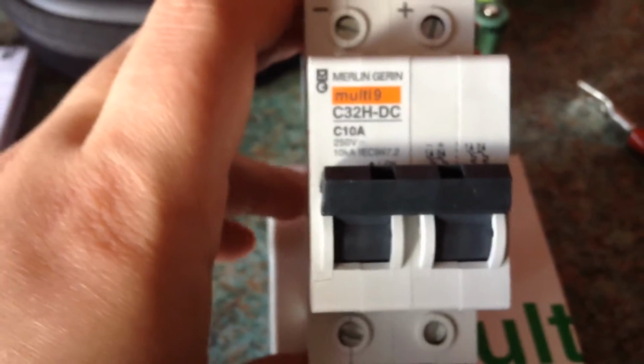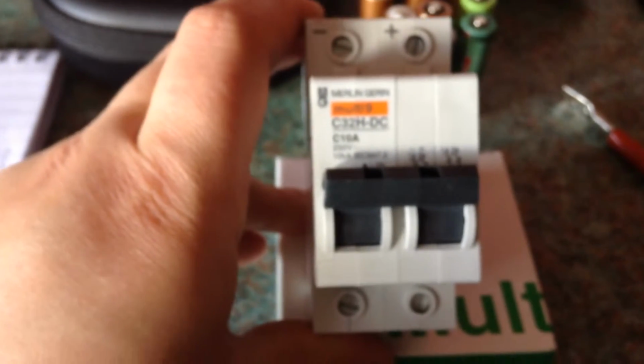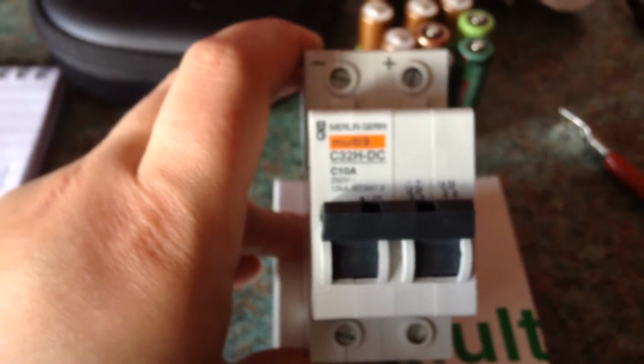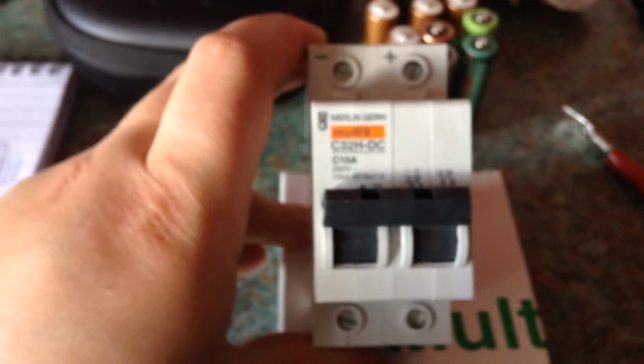One important thing to note is that you must not use AC circuit breakers on DC circuits - they are not compatible and not made to do the same job. It's harder for a circuit breaker to interrupt a DC circuit than an AC one, because an AC circuit has a sine waveform, and at a point in the cycle there is 0 volts, which is when the breaker opens the circuit. That's fine for AC, but in DC there is no 0 point since there's no waveform - current flows at maximum voltage and current all the time, so you need special DC breakers.